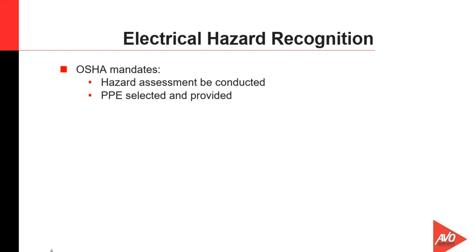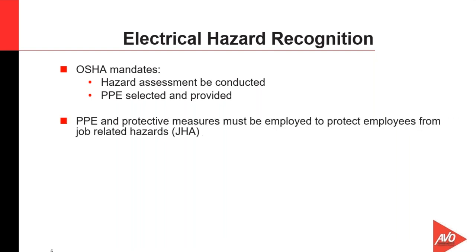OSHA mandates that electrical hazard assessments be conducted under OSHA 29 CFR 1910.132. It's very explicit as to the company's requirement for conducting hazard assessment in the workplace for the tasks that are actually done. In order to assess PPE and provide PPE, the assessment has to be completed. These protective measures need to be employed based on what employees actually do.